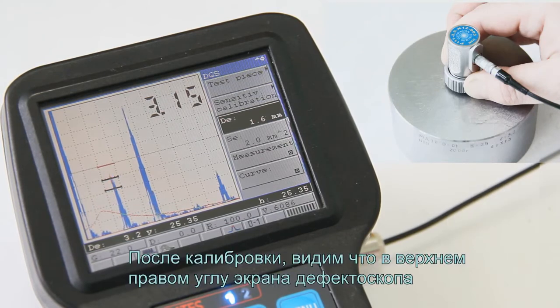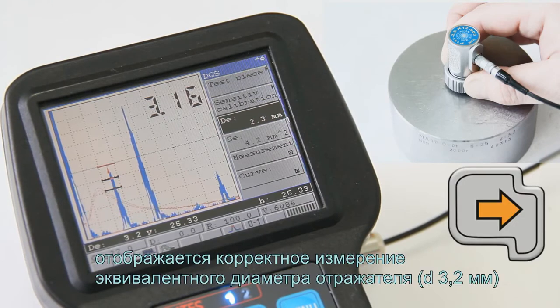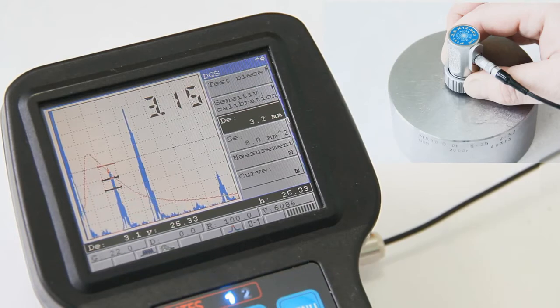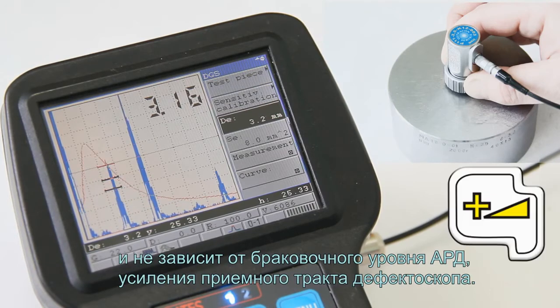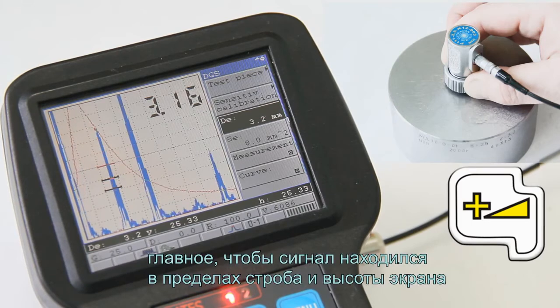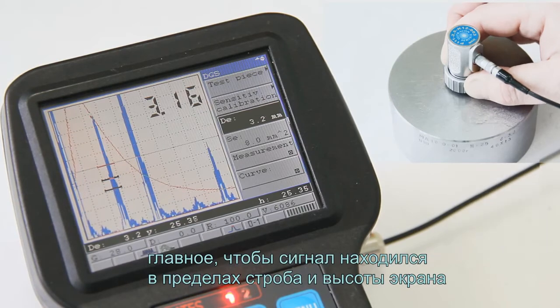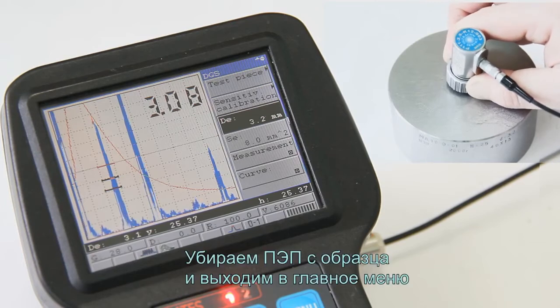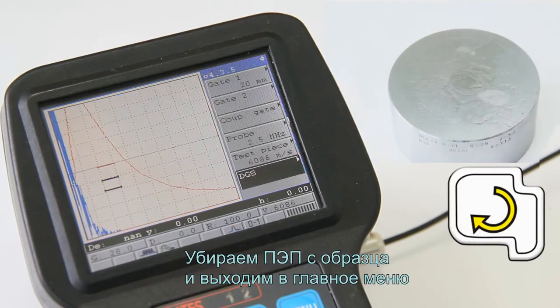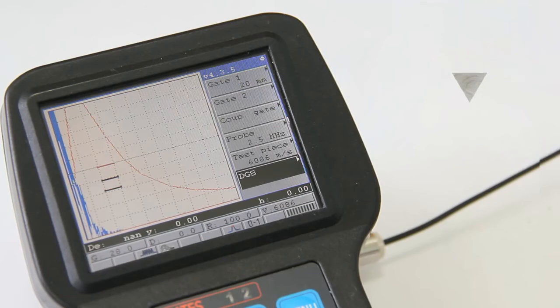After the calibration, the correct measurement of equivalent reflector, diameter 3.2 mm, is shown in the right up corner of the Flaw detector screen and does not depend on the DGS acceptance level and on the gain of the Flaw detector reception path. It is essential the signal to be within the gate and the screen height. Remove the probe from the block and exit to the main menu.